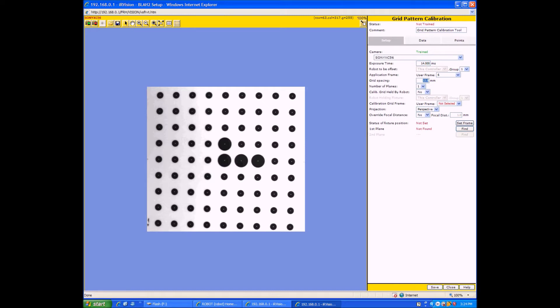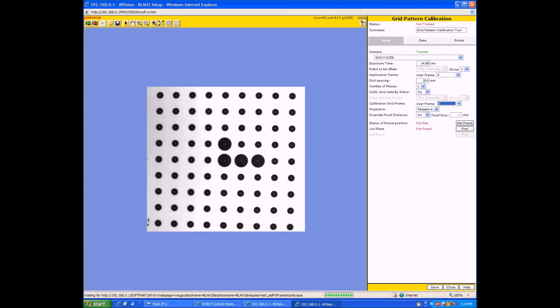You're going to want to enter in the grid spacing — this one was 20 millimeters, but it's written on the calibration grid. We also want to make sure that our application frame is the same number as our calibration grid frame; in this case that number will be six. Then override the focal distance to 16 millimeters, hit Set Frame, then hit Find.